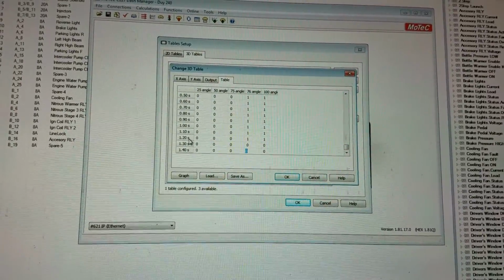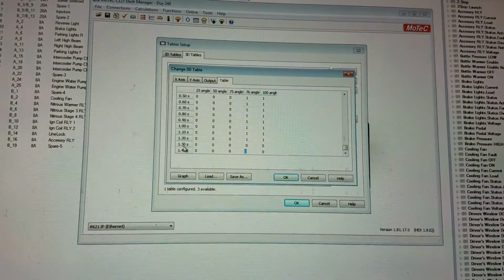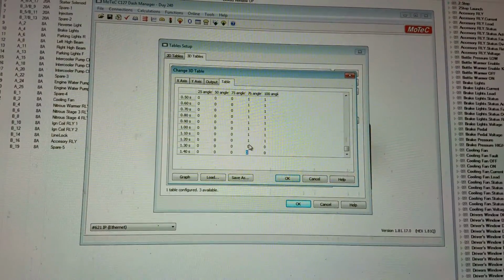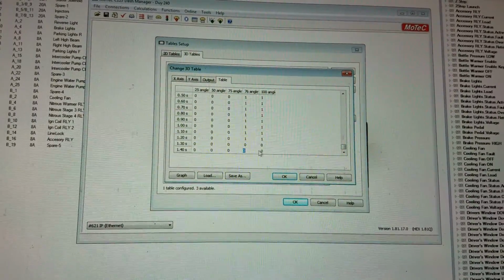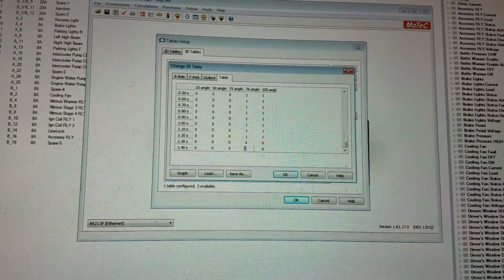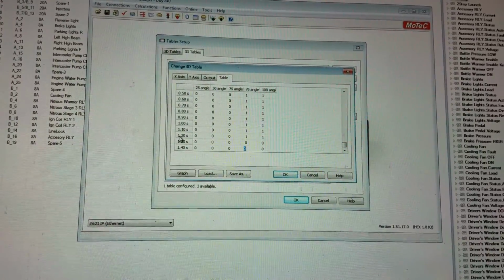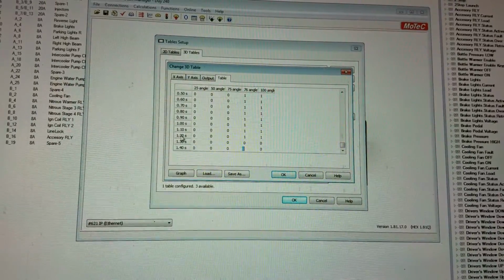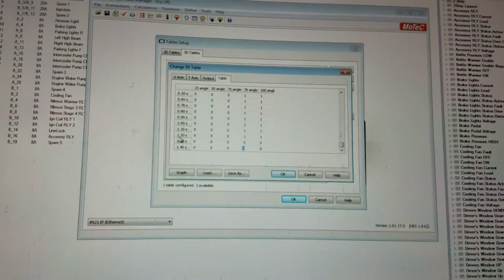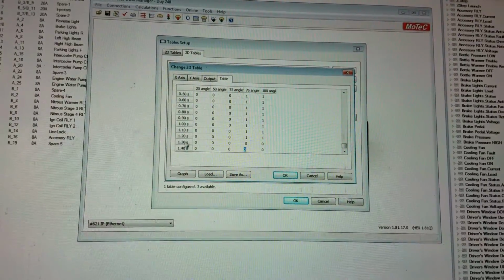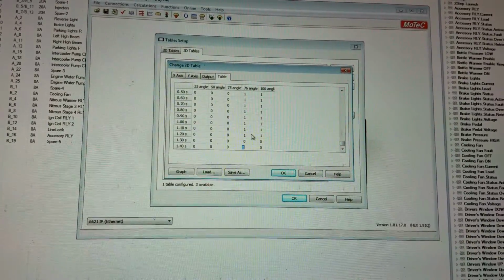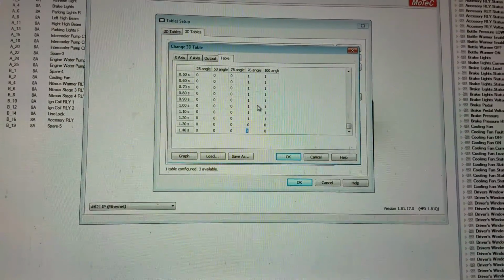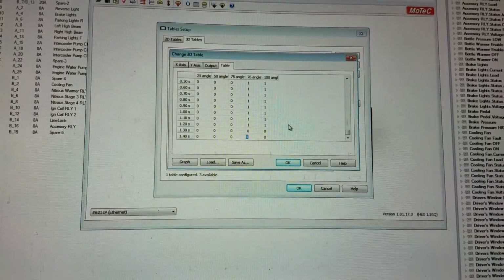Then once you pass, it's going to interpolate a little bit, so it'll probably shut off at about 1.25. It'll be completely off. It'll shut off the CO2. Now I can obviously change these breakpoints. I could make this 1.21, 1.201, so it's within a hundredth of a second or a tenth of a second, however I want to do it. But I don't think this particular situation needs to be that accurate.